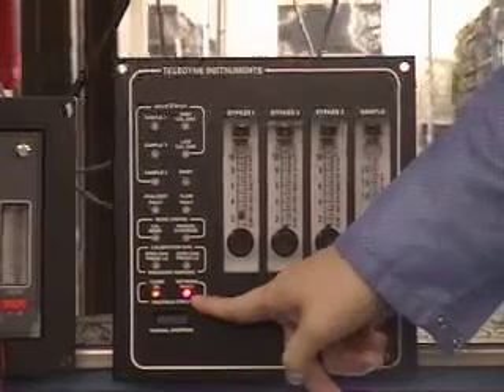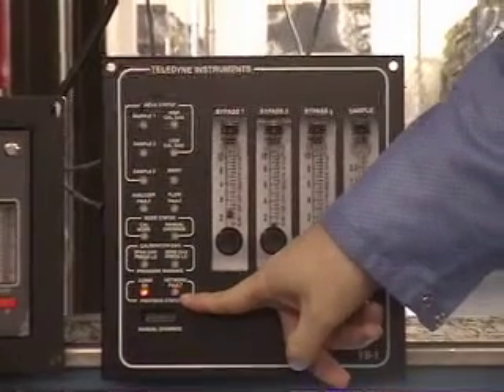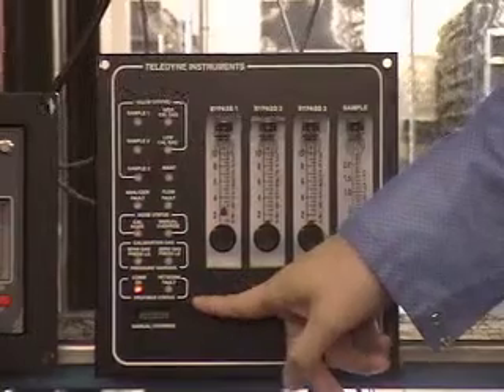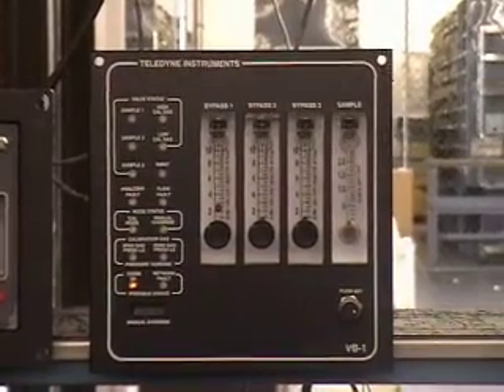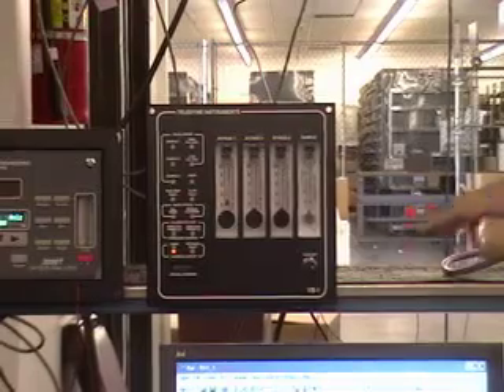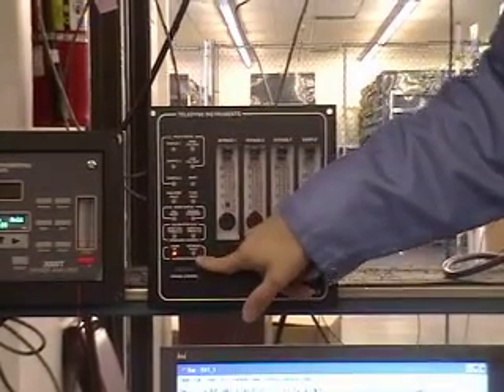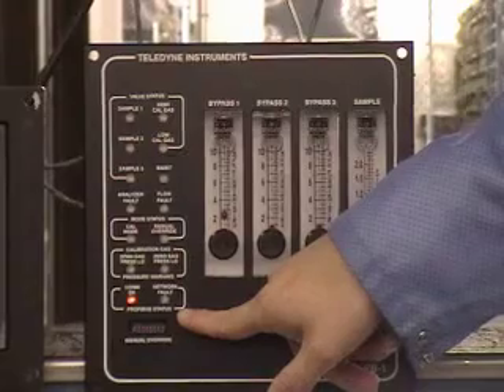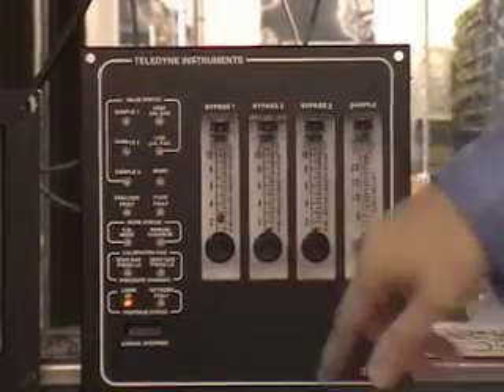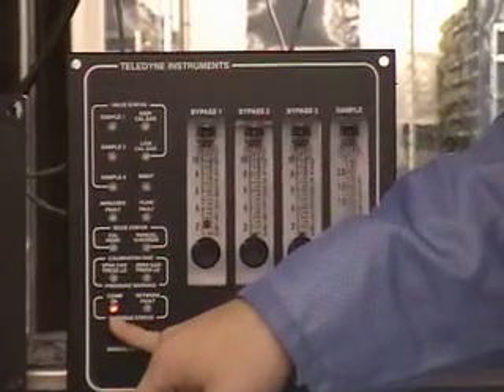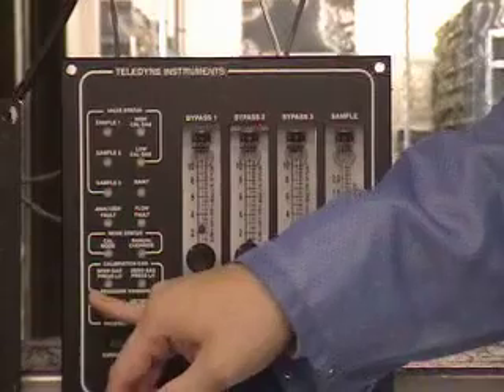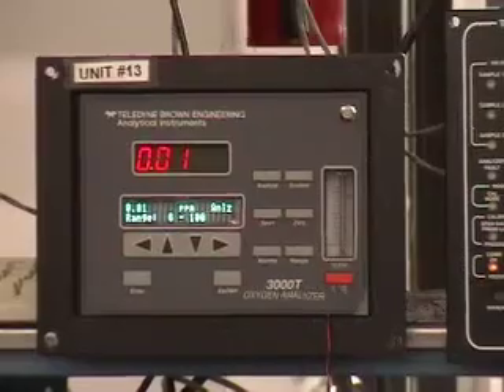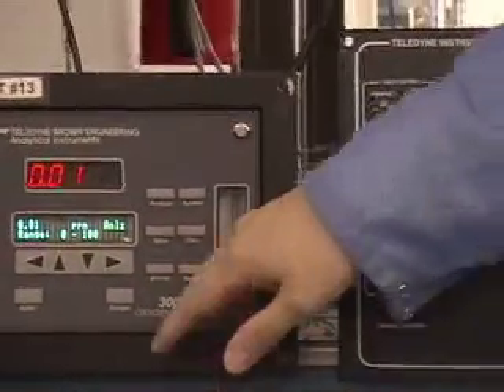The PLC hasn't finished booting up yet, so the network fault light is on. And now the PLC finished booting up, so the PLC came to full power. Now there is a connection, so the network fault light went off. So that means we have communication between the BB1 and Step 7. And the yellow light here, communication okay, means we've got RS-232 communication between the BB1 and the 3000T oxygen analyzer. So this unit is receiving communication through the RS-232 and is communicating to the network.